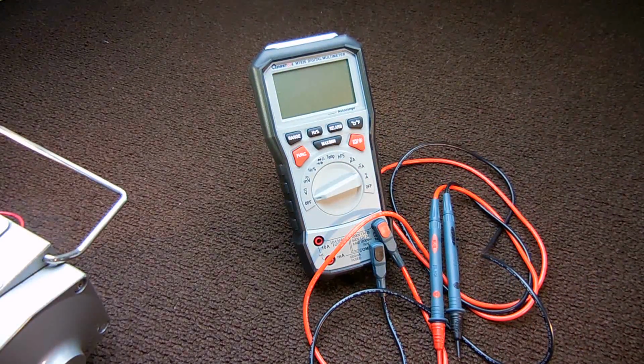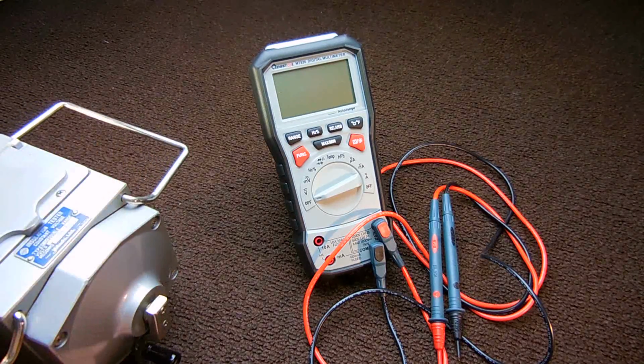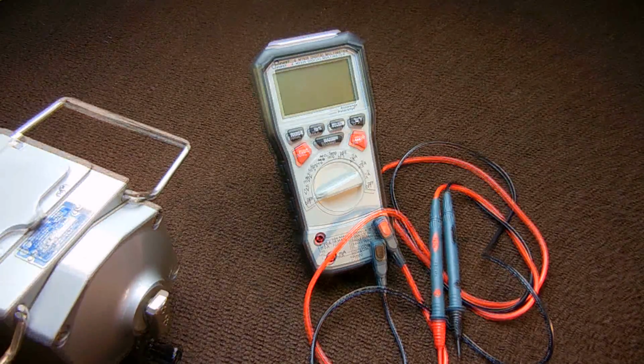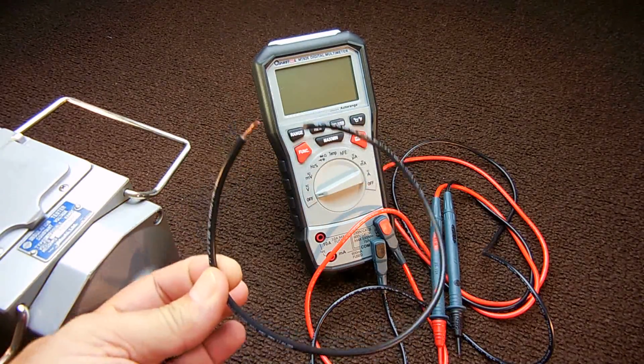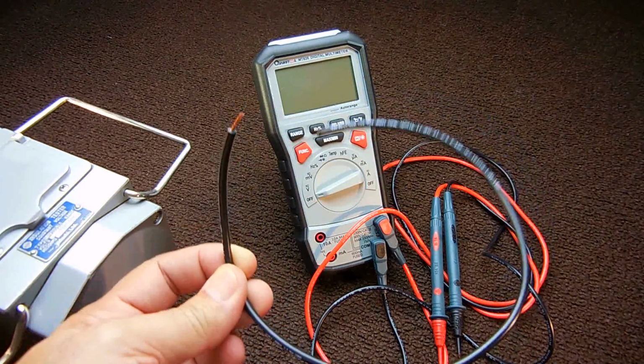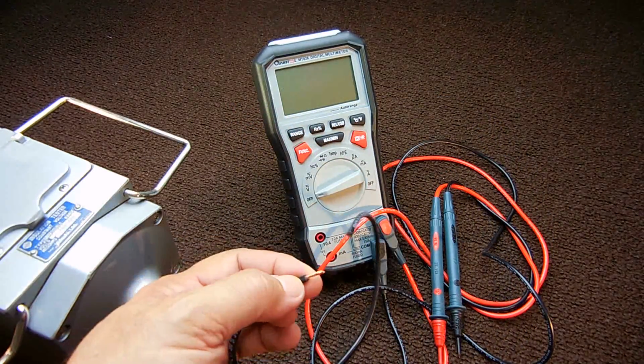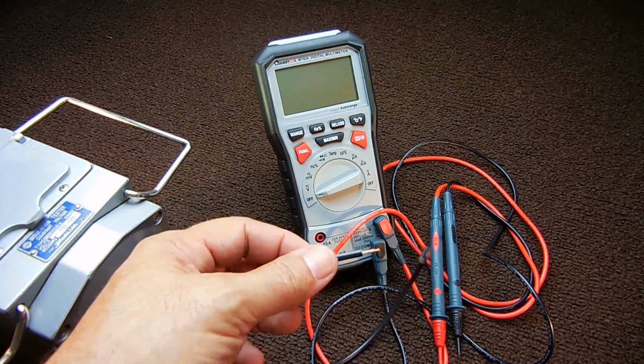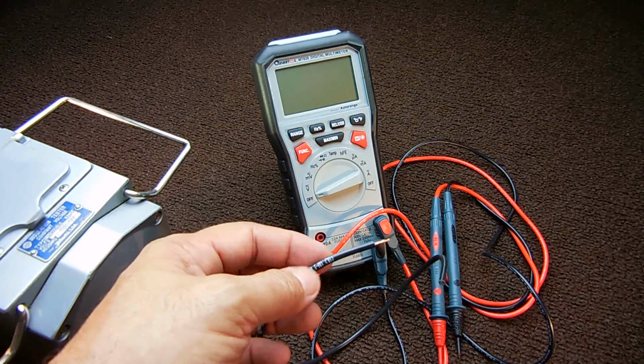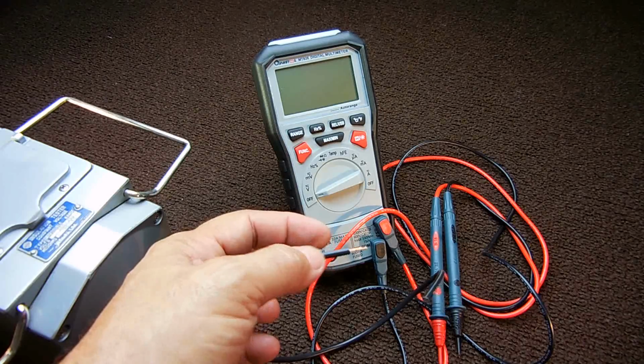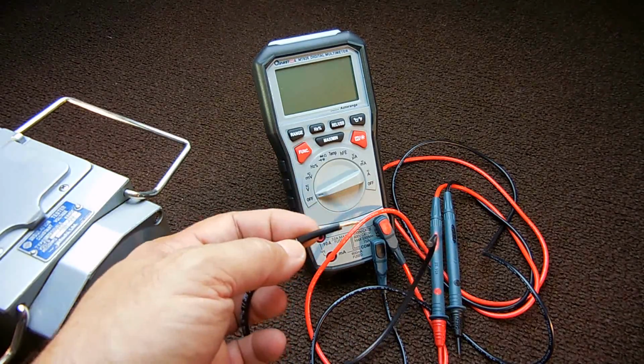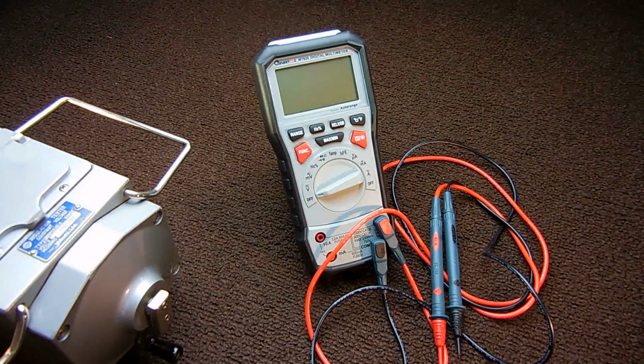The reason being is if you use an ohm meter, it's only going to be checking the wire or the windings of a motor using very low voltage of around 9 volts. The Megger is going to be using a much higher voltage. It's going to be using anywhere from 250 all the way up to 1000 volts, which is the electronic model. This one does 250 and 500. What the insulation tester does, it applies a potential or voltage to the wire or winding that's under test. And because you're putting pressure or voltage on that center conductor, if the insulation is deteriorated, cracked, dried out, and susceptible to the voltage leaking through it, by applying that higher voltage, it's going to show up. With a regular ohm meter like you see here, you're not going to be able to see that.